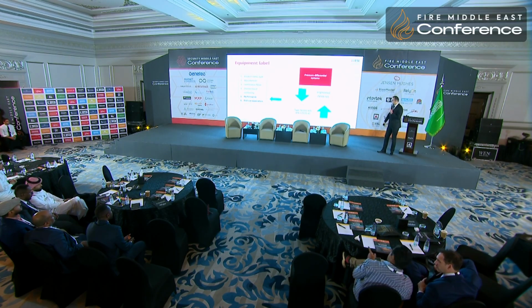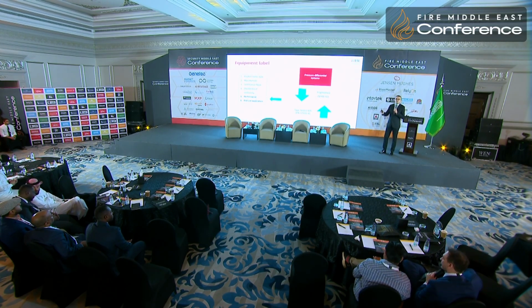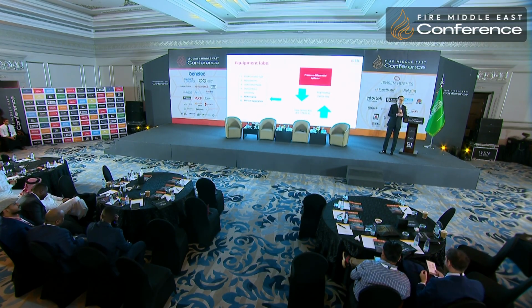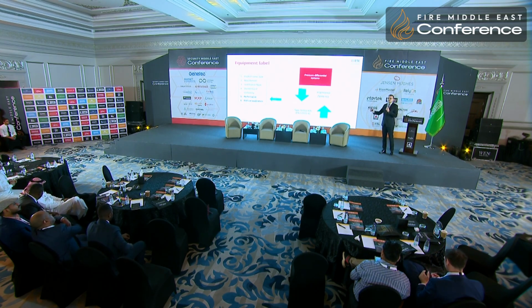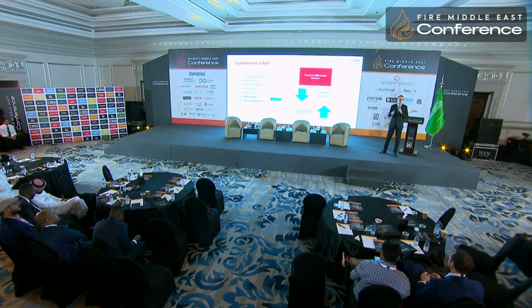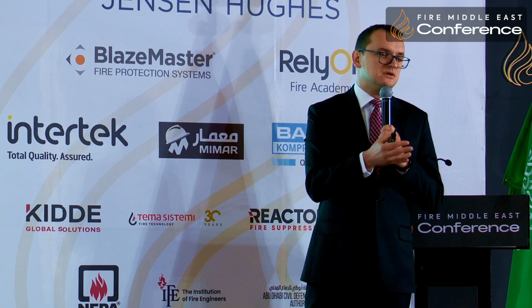Coming from Europe, there is the EN 12101 Part 6 standard. I wanted to share that information with you if you are dealing with such systems. The full system can't be tested, but sub-assemblies of the system can be pre-tested and certified. Then, with such components introduced to the building and their performance known, there are higher chances that at the commissioning stage the system will achieve its functional objectives.